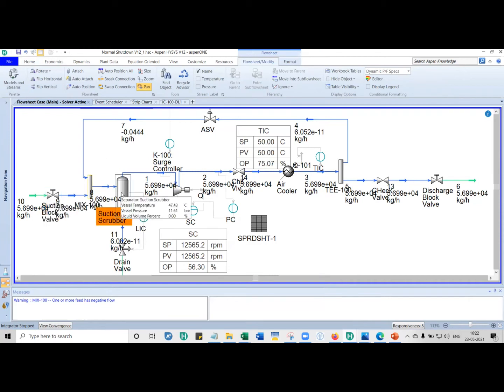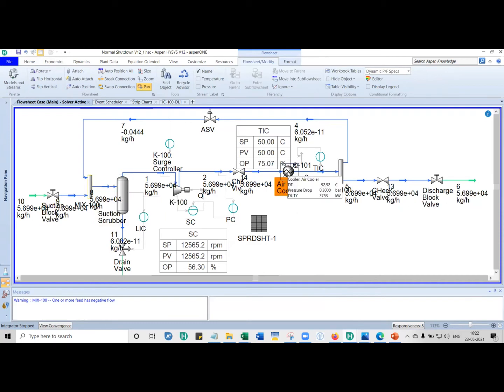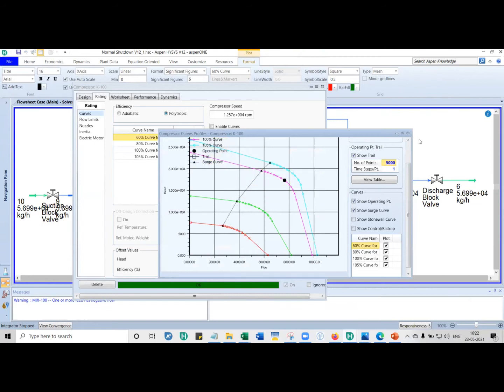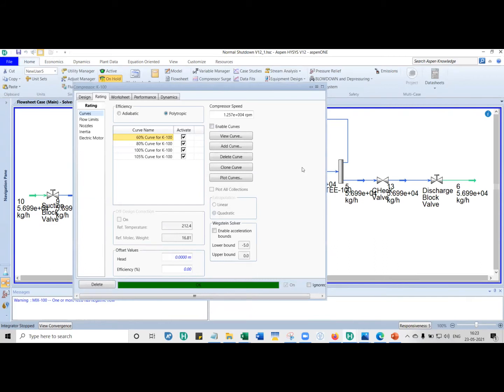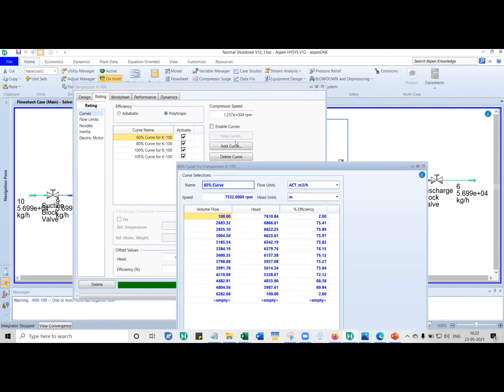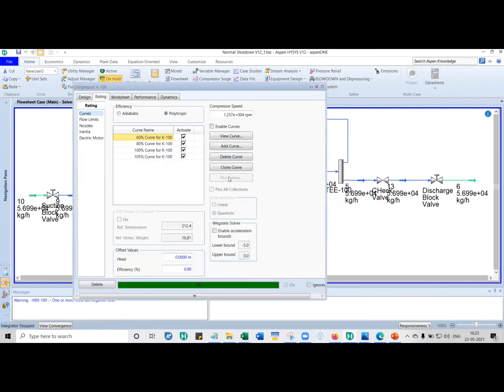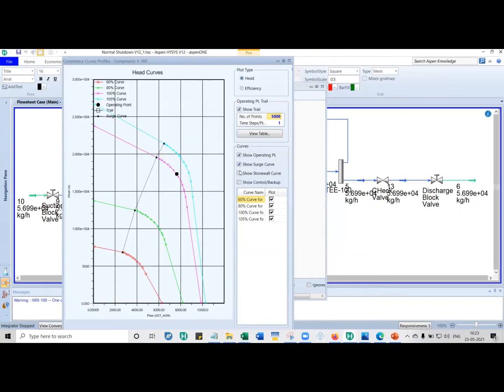For suction scrubbers you have to give the volume. For the air cooler you have to give the volume and also the loss coefficient. For the gas compressor, you have to put your performance maps. You need three pieces of information: polytropic head for a given volumetric flow rate, and polytropic efficiency. These three parameters are needed, and for each speed you enter them in HYSYS. The actual data is from the compressor — but what are those extra two points that were manually entered?